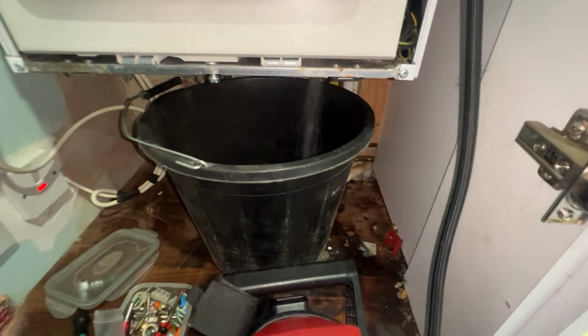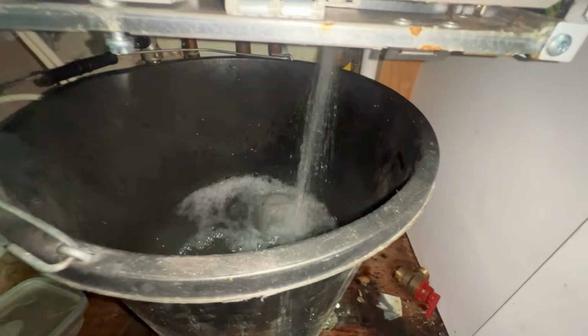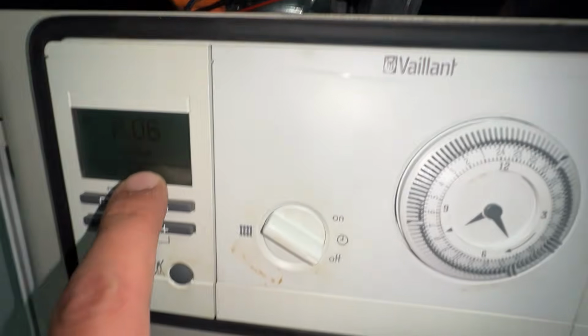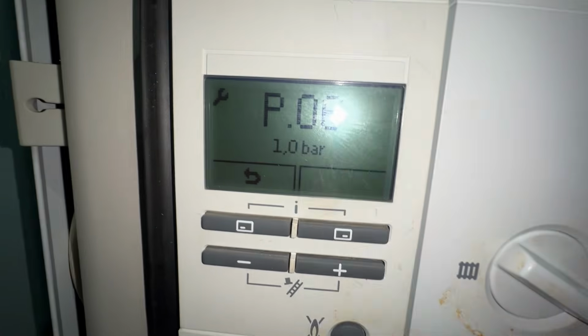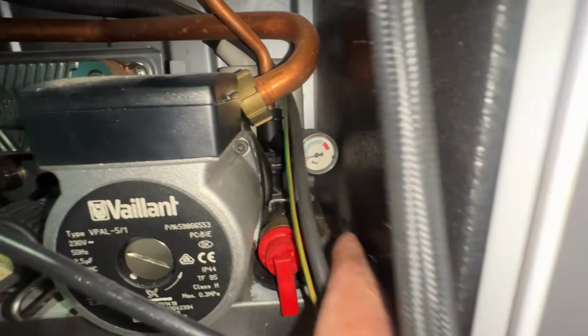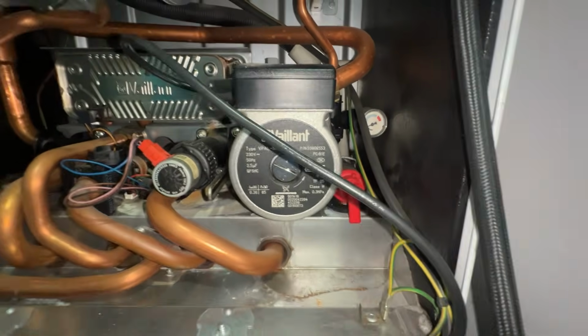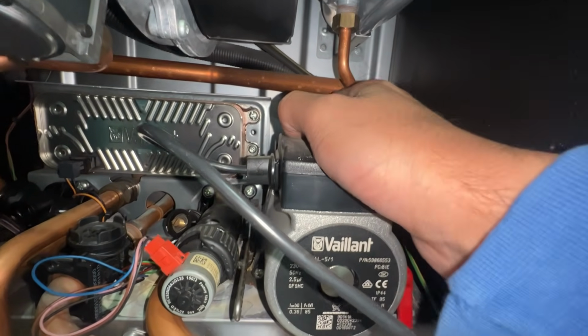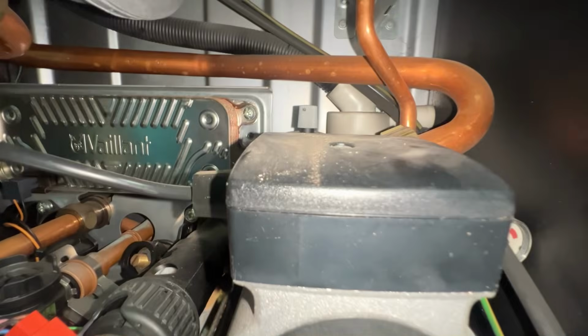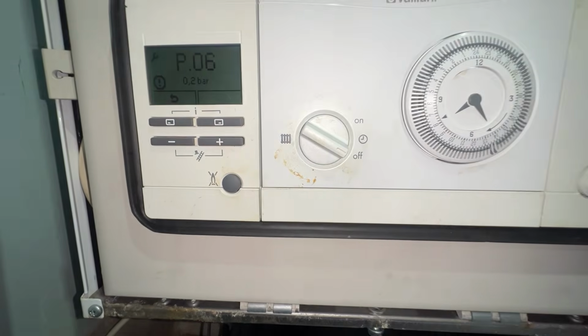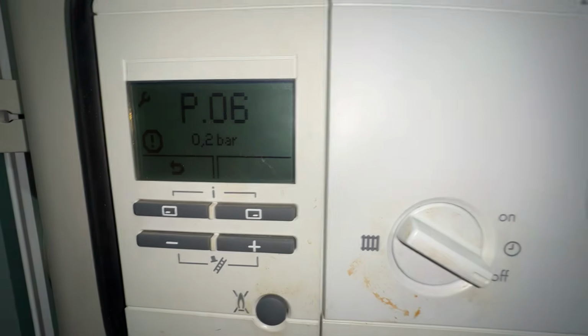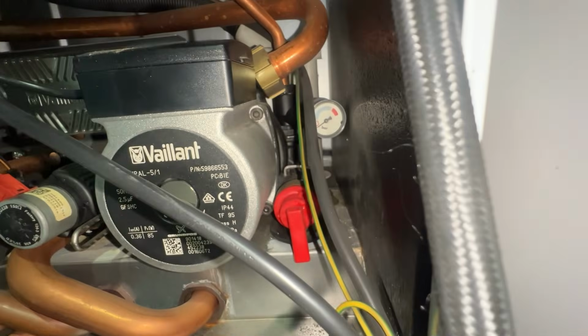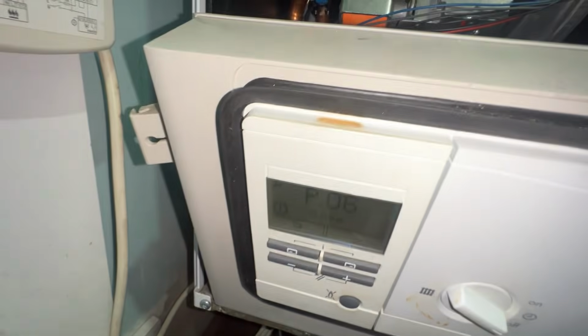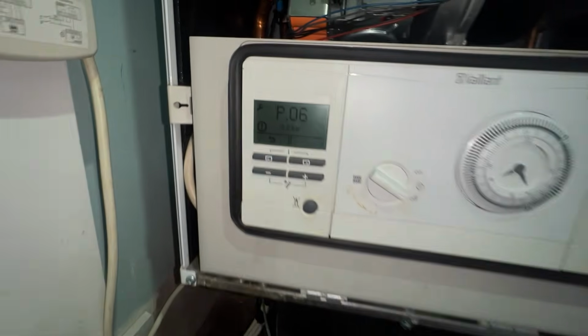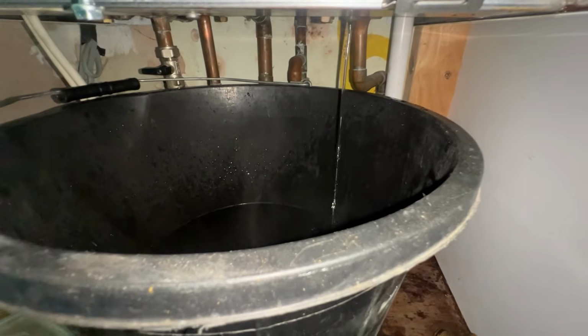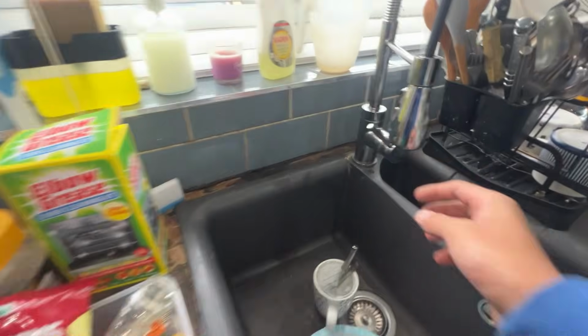Wow, did you see that? I know it pushed a load of water out. Pressure's gone to 1.1. Right. I didn't make sure that was open, should have opened that first. That's better, 0.2. Nothing in the boiler now. That's been drained. Open hot water.